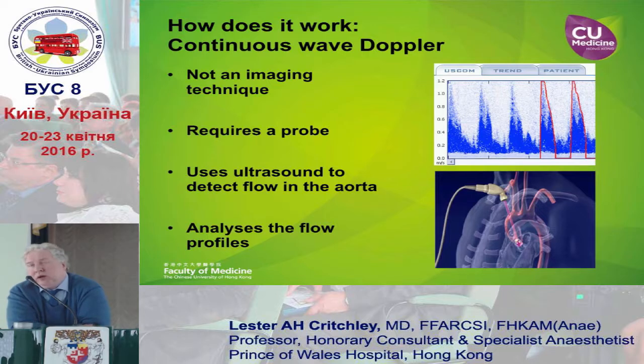What is shown on the screen is a flow wave that goes across the screen with time. By outlining each flow wave and measuring its area, you get stroke volume. So it requires a probe that is handheld and has to be manipulated to focus the beam.